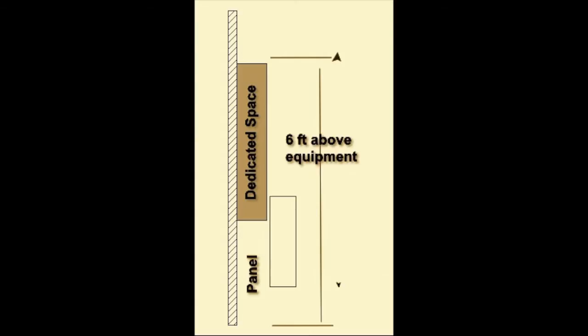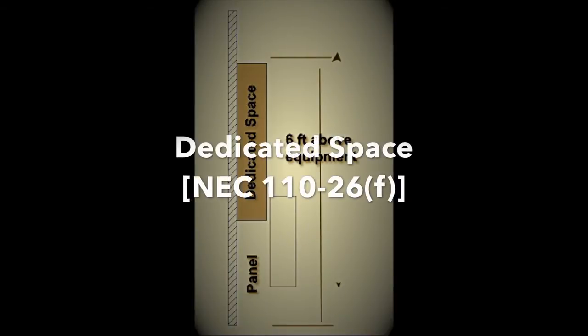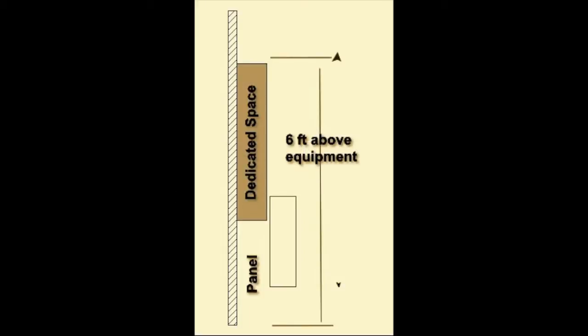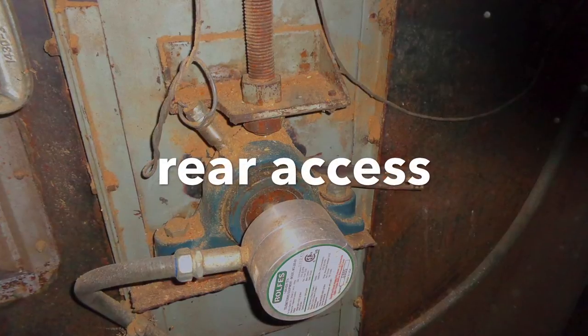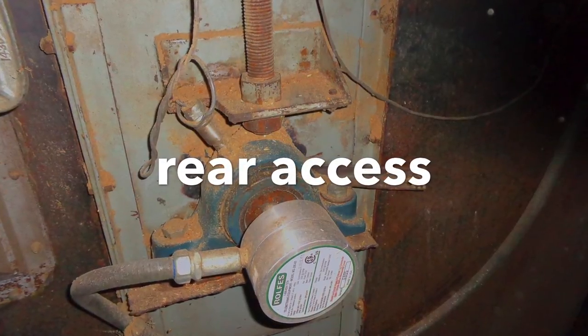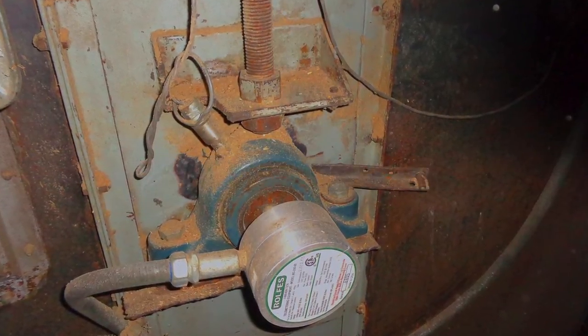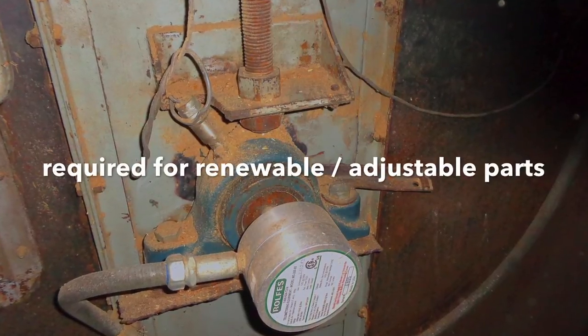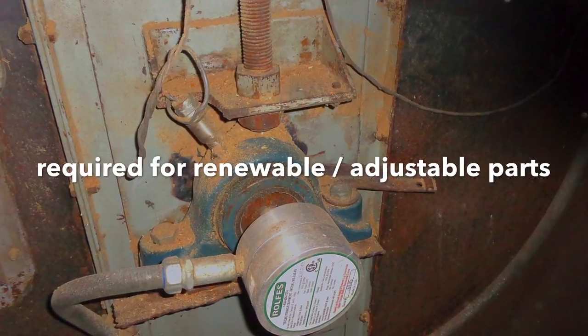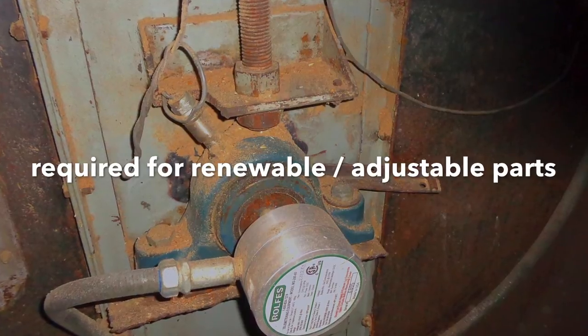The dedicated space, according to NEC 110.26(F), is required to be the width and depth of the equipment extending from the top of the equipment 6 feet or to the structural ceiling. Rear access to equipment will be the same as access requirements for the front, only if there are renewable or adjustable parts such as fuses, switches, or connections that are accessible from the back.